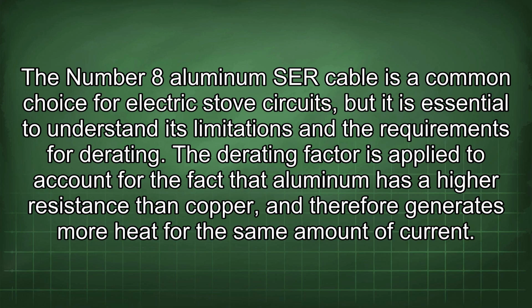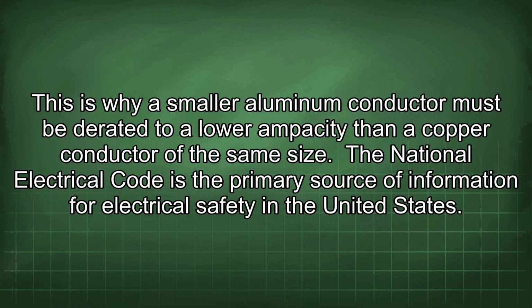The derating factor is applied to account for the fact that aluminum has a higher resistance than copper, and therefore generates more heat for the same amount of current. This is why a smaller aluminum conductor must be derated to a lower ampacity than a copper conductor of the same size.